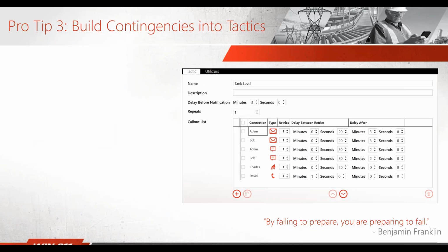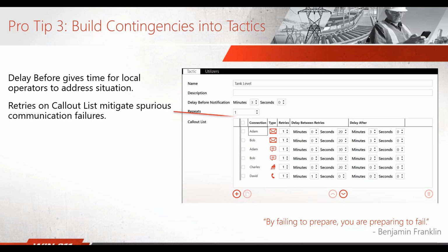Tip number three, build contingencies into your tactics. You can use delay before on your basic tactics to give some time for operators to address the situation. So perhaps an alarm goes off. You don't want to send a notification out right away. You can wait 3 minutes for an operator in the plant to react. After 3 minutes goes by, we can go ahead and start notifying people. We can use retries on the call out list to mitigate some failures. So if we try to email Adam and the email server is unavailable, we can go ahead and retry that. So use retries to make multiple attempts on notification.